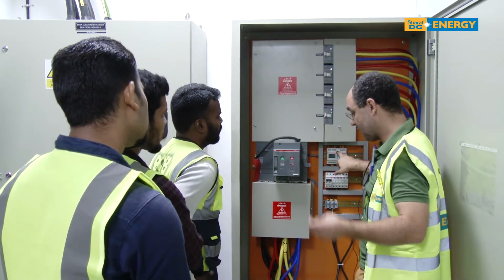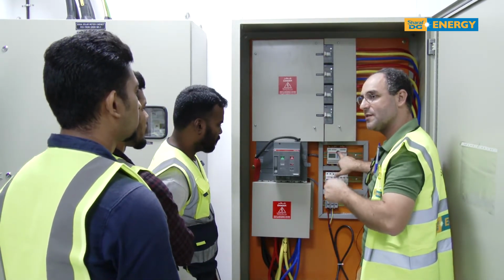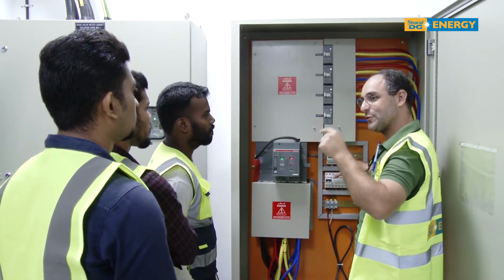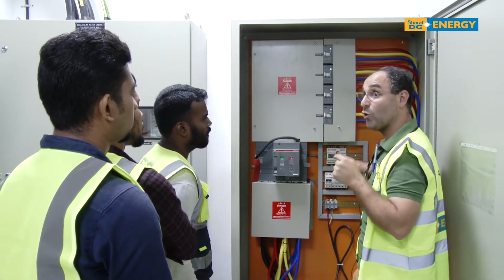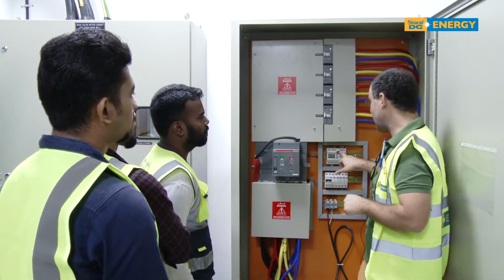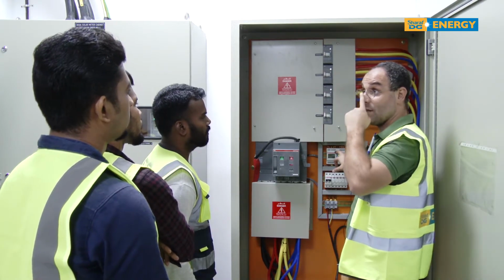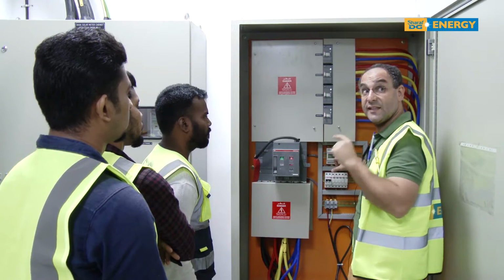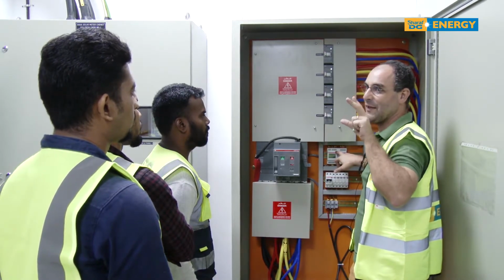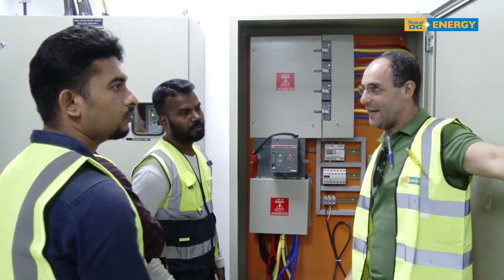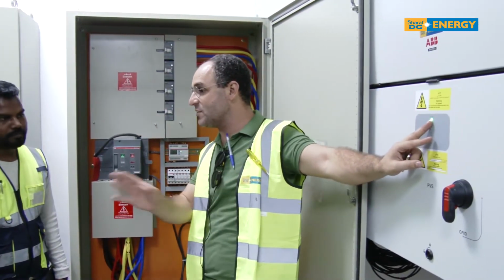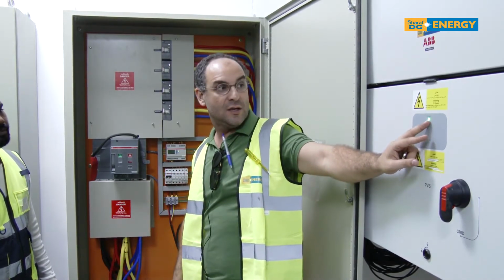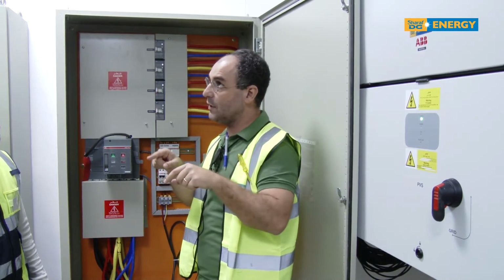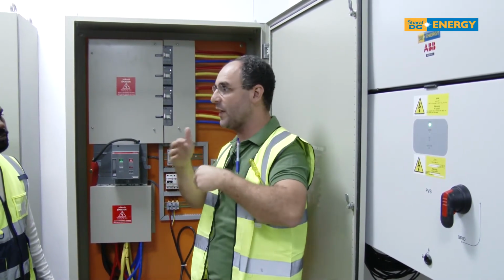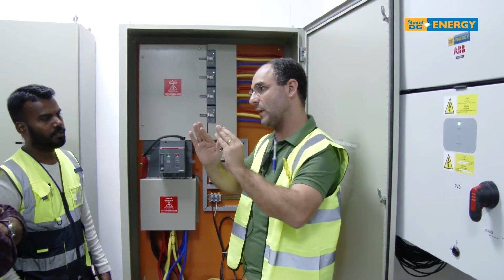Okay? So in the next session that we're going to have, we're going to force the system to simulate over voltage, over current, and so on, and simulate a fault. We will simulate a fault by removing one of these cables, right? Simulating a fault in the system. So what you're going to see is that the inverters will be automatically blinking. You see here? Now it's steady. You have only 3 indicators on this machine. The rest you have to take from the connection to the computer, okay? If it is blinking, it means it is doing the internal checkup prior to hooking to the grid. If it is steady, it means it is hooked to the grid, exporting.